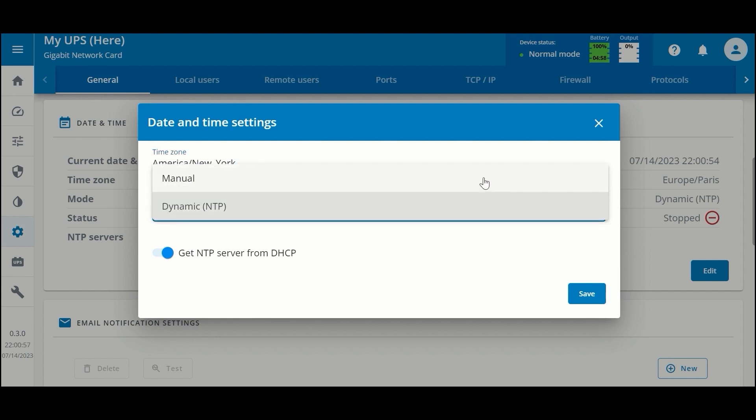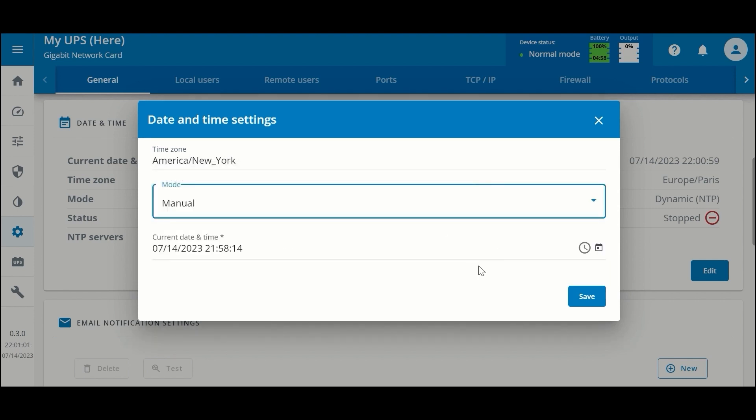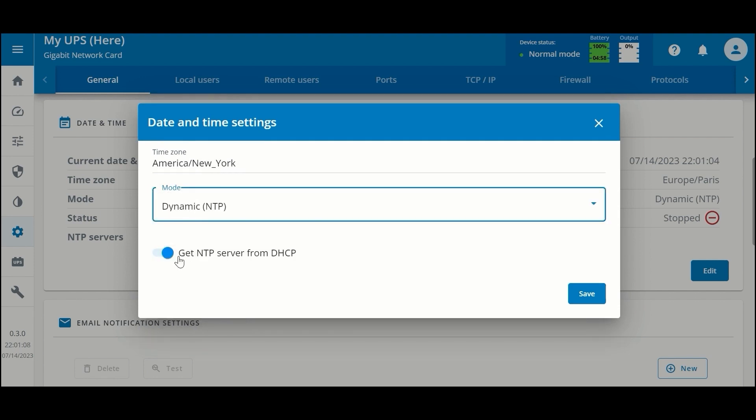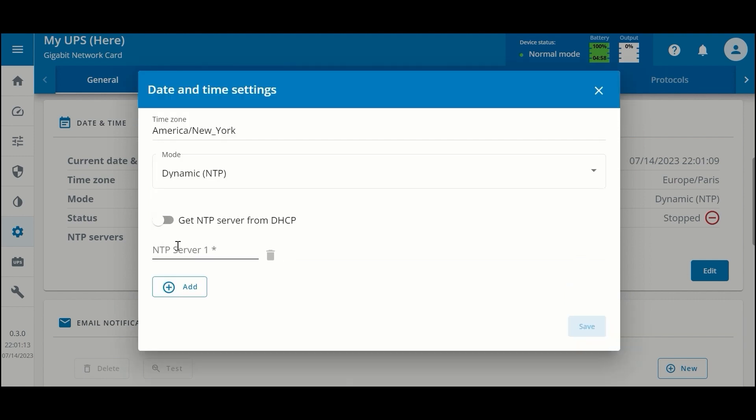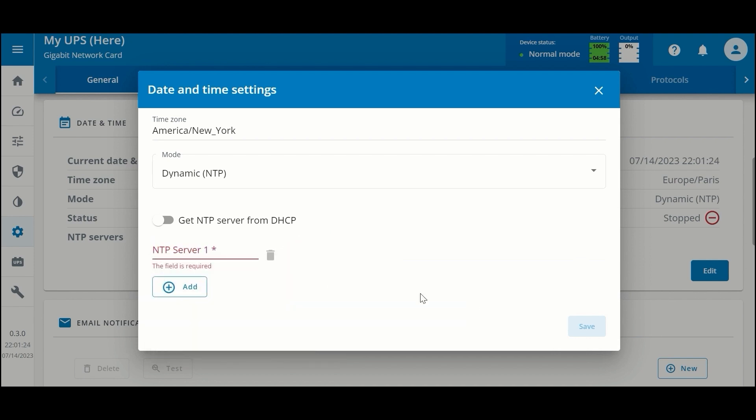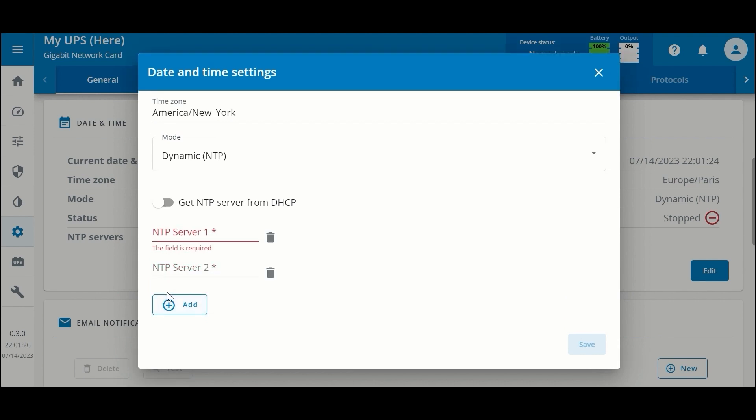You can change this to manual, in which you would manually set the date and time, or you can disable getting the NTP server from DHCP and manually enter the NTP server. You can add additional NTP servers as required.